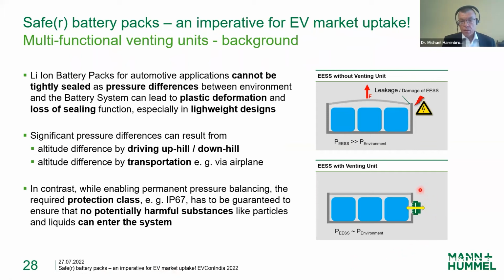The pressure balancing is required because if you would have a completely sealed battery pack, and different air pressure inside and outside of the system, for example, because of driving uphill or downhill or transportation via airplane, the resulting pressure differences will lead to forces, which can lead to deformation of the battery pack housing or also to leakages. So what the venting unit does is enable the exchange of air between the environment and the battery pack.